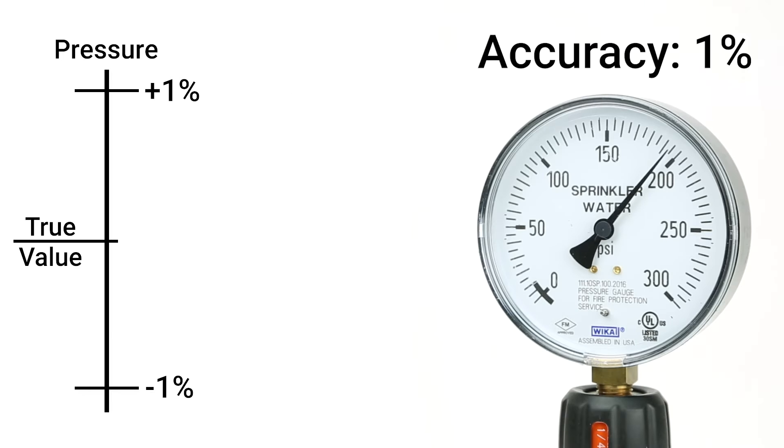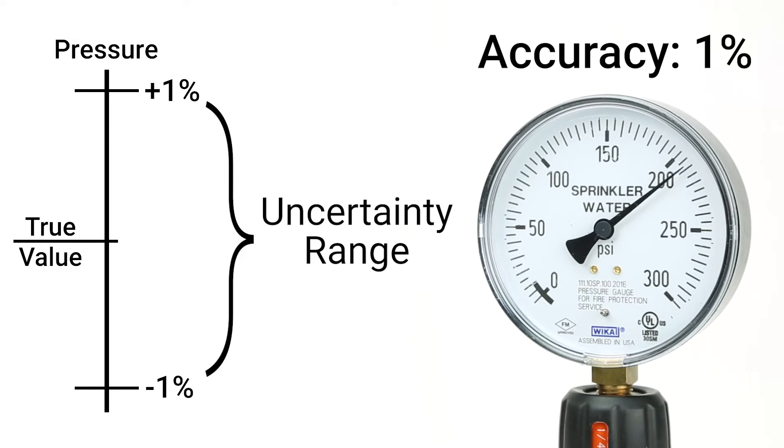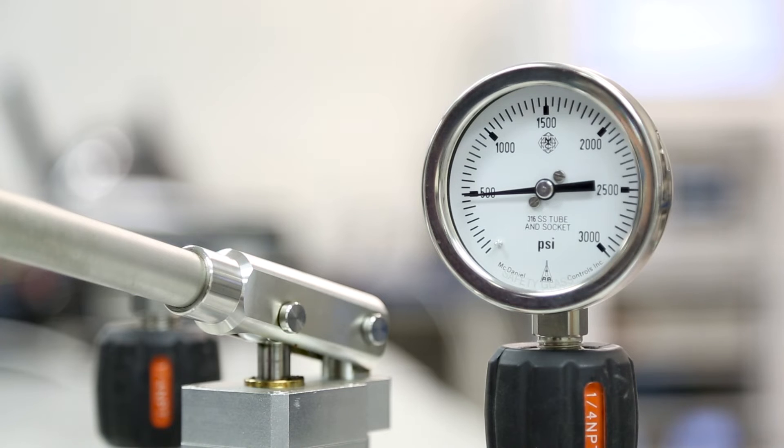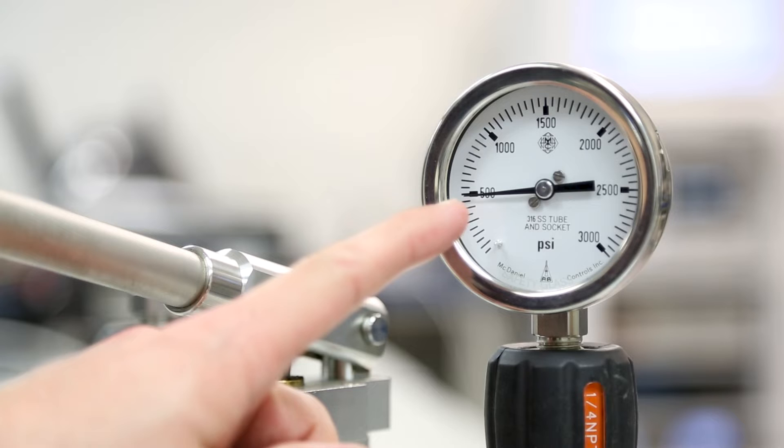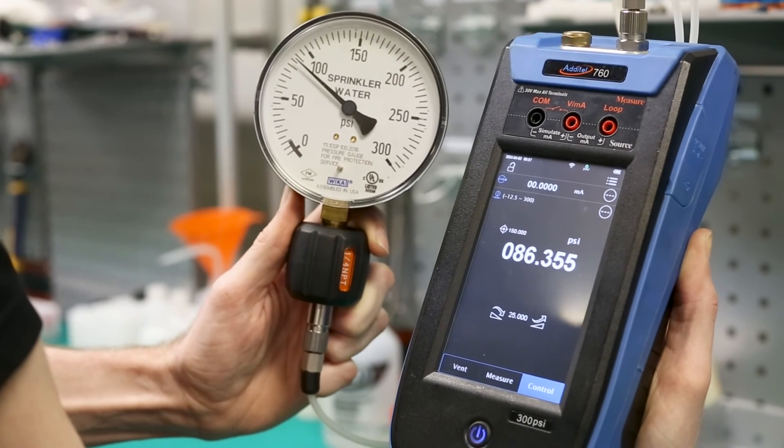So while the specified accuracy of a device is technically an uncertainty range, it does not always account for the full uncertainty of a measurement. A simple way to think about it is that accuracy is usually used in measurement, while uncertainty is usually used in calibration.